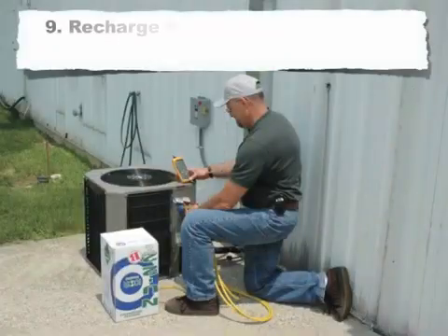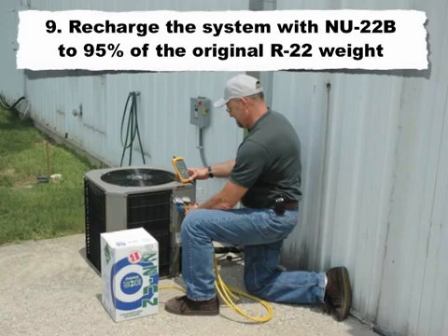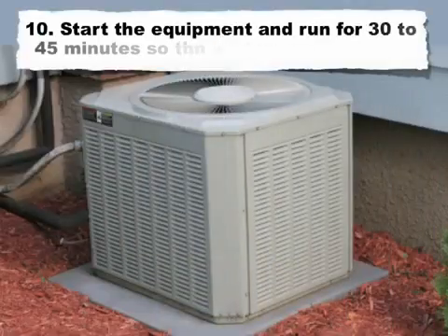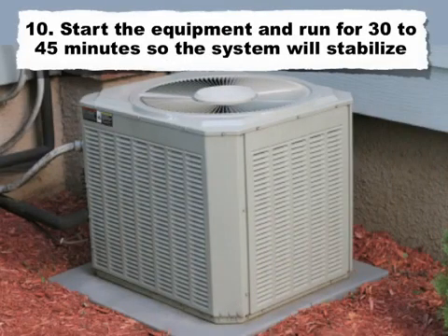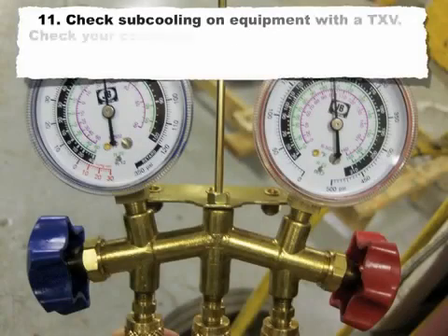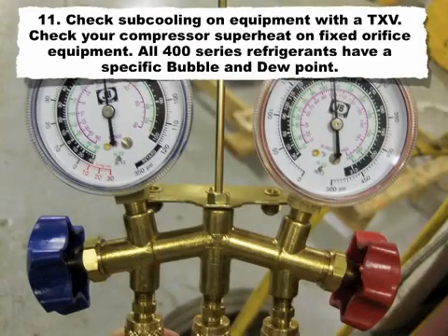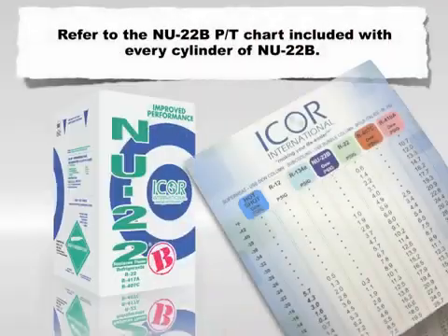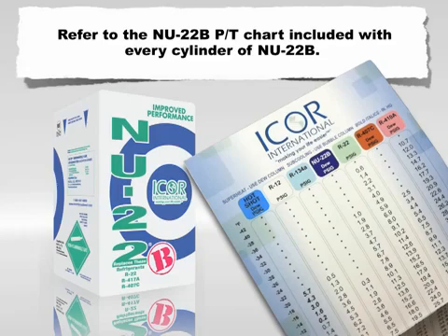Step 9: Recharge the system with NU-22B to 95% of the original R22 weight. Don't charge by sight glass, as it could lead to an overcharge. Step 10: Start the equipment and run for 30 to 45 minutes for the system to stabilize. Step 11: Check subcooling on equipment with a TXV; check compressor superheat on fixed orifice equipment. All 400-series refrigerants have a specific bubble and dew point. Refer to the NU-22B PT chart included with every cylinder of NU-22B.